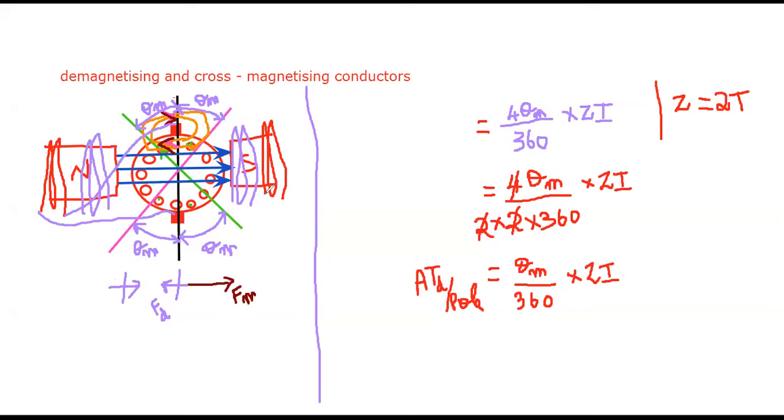If we connect it like that, what happens? If the load increases, automatically the current flowing through the extra winding will also increase. So the amount of opposing demagnetizing flux produced will be equal to the amount of demagnetizing flux in the armature. So they will neutralize each other and the demagnetization effect will be neglected, right? This is how the demagnetization effect is neglected here. And this is our final formula for the demagnetization effect, which is very simple.